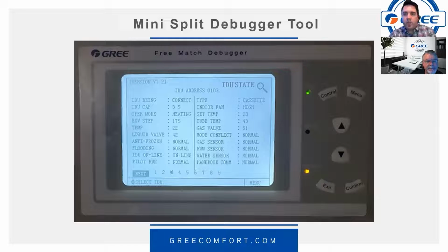Just to clarify, there's the single zone and then the multi-zone debugger. The single zone is going to read whichever unit you connect it to, such as the outdoor, or if you connect it to the indoor, it's going to give you the indoor readings. The multi-zone, as you can see in this example, gives you indoor and outdoor readings. So you don't have to run up and down the steps trying to determine if unit A is in high fan speed mode and what the indoor temperature is on it.